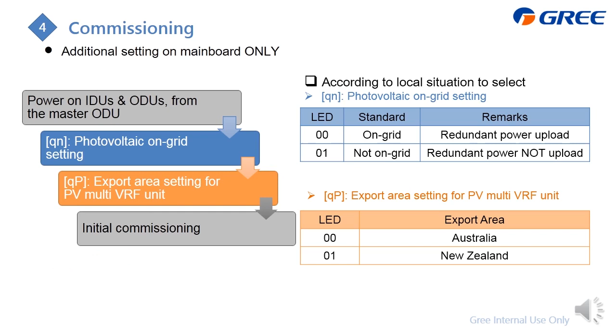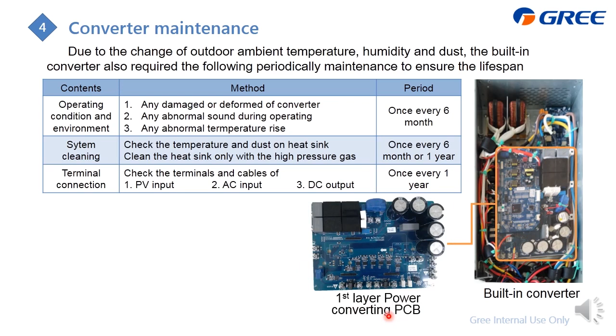As for the maintenance, due to the change of the outdoor ambient temperature, the humidity, and also maybe the dust situation, for the VRF it is almost no need to do the maintenance, but inside the converter, this is the converter, you need to do the periodical maintenance. Actually, for this converter, there are 3 layers. This is the built-in. Just open the panels, and inside this one, this is the first layer, the power converting PCB. Here there is a second layer, the sampling PCB. And at this part, this is the third layer, the CPU PCB.